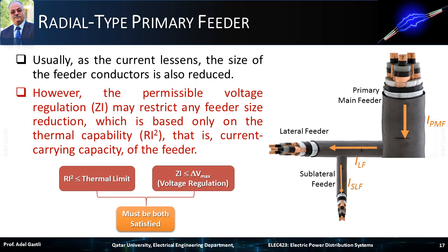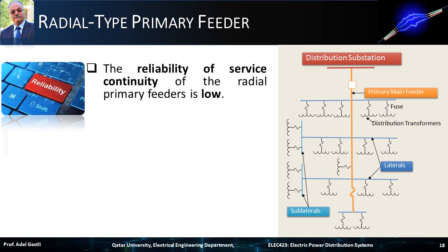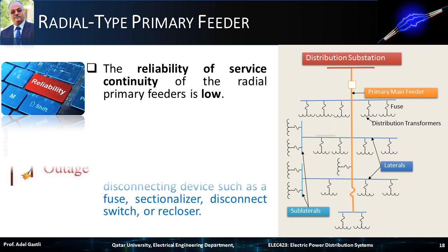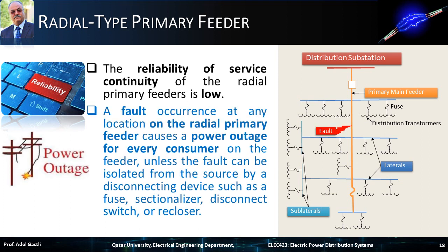As mentioned in the previous chapter, the reliability of service continuity of the radial primary feeders is low. Indeed, a fault occurrence at any location on the radial primary feeder causes a power outage for every consumer on the feeder, unless the fault can be isolated from the source by a disconnecting device such as a fuse, sectionalizer, disconnect switch, or recloser. In this case, a proper coordination of protective devices responses is very essential in order to minimize the number of affected customers.